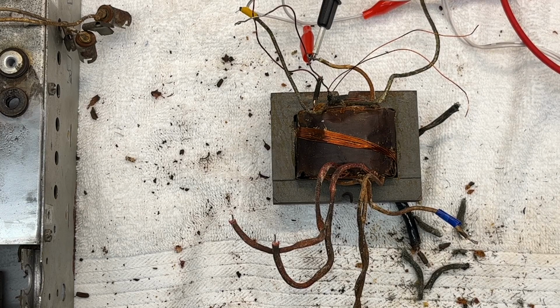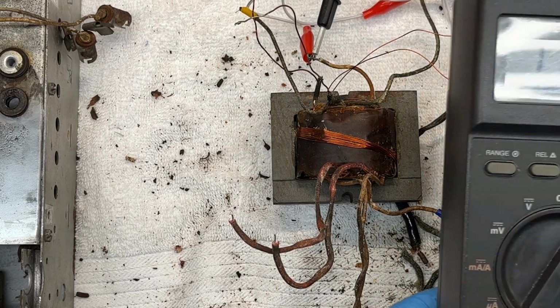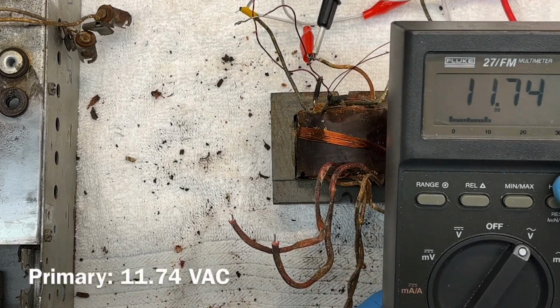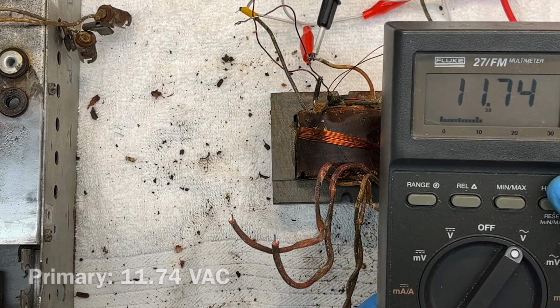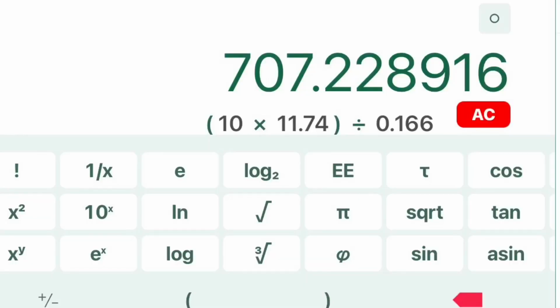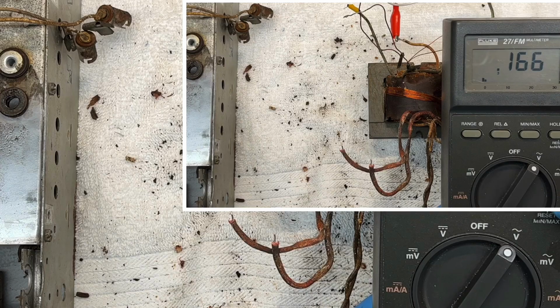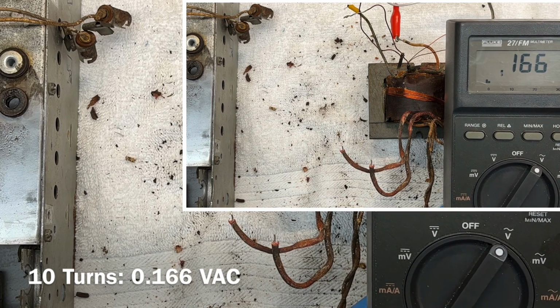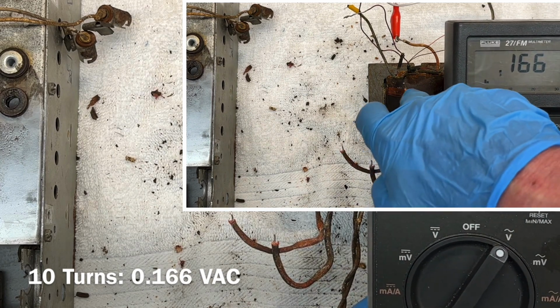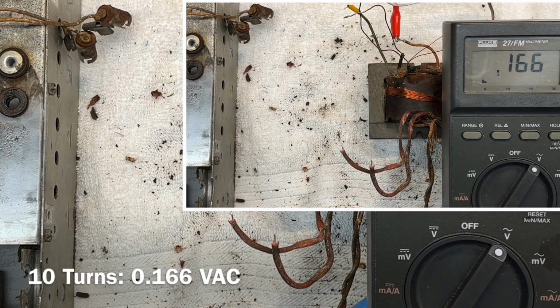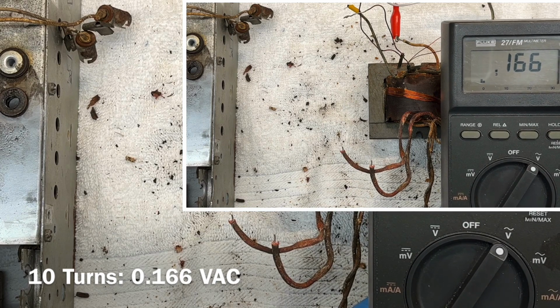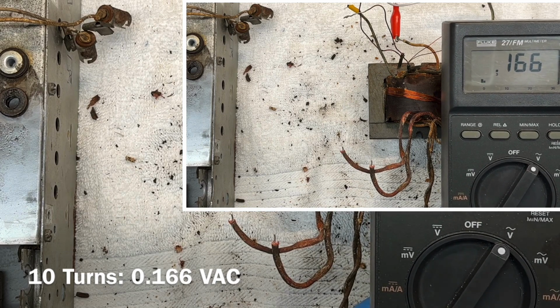And then I'll measure the voltage on the primary side. In addition to the 10 turns, we can do some simple math, as you're seeing here in the calculation, and use this data to determine the number of turns for the primary. Then we can find out the turns per volt and use that information to determine the number of turns for each individual winding.